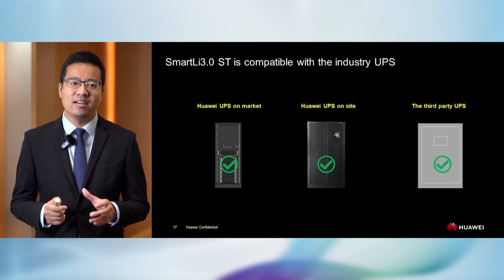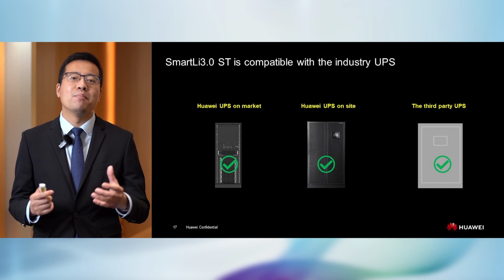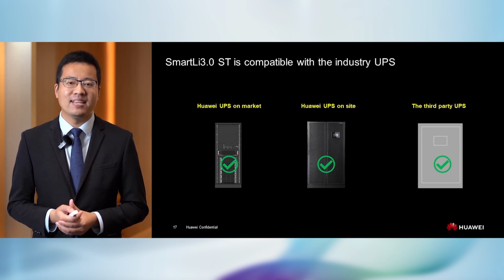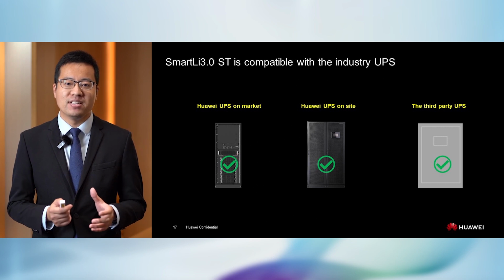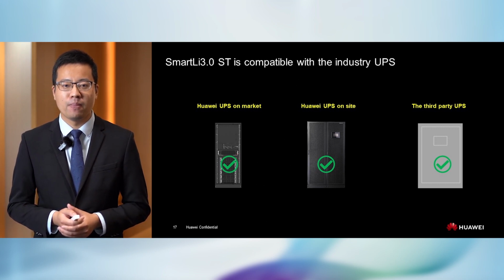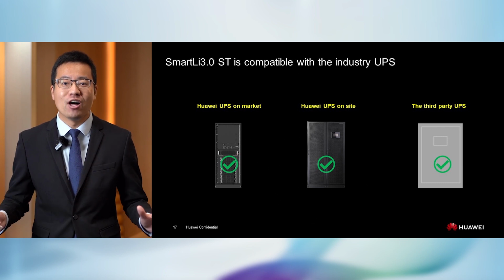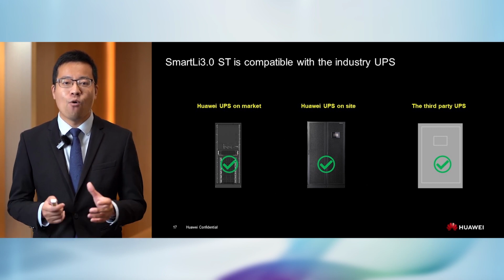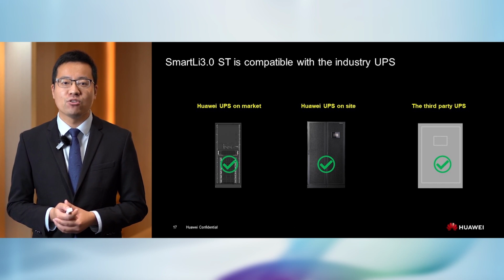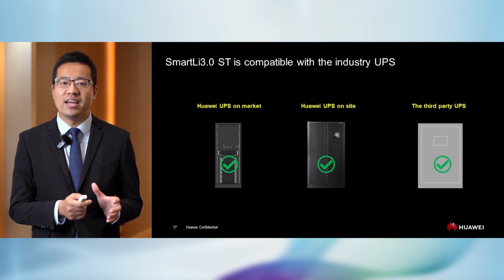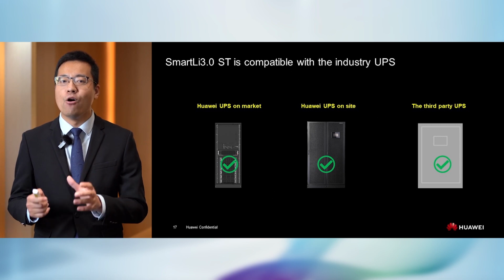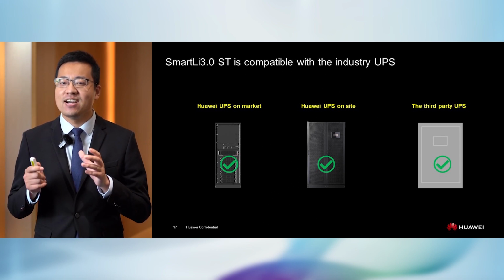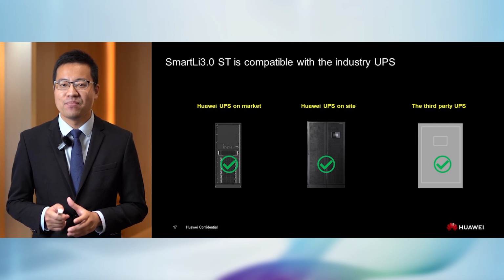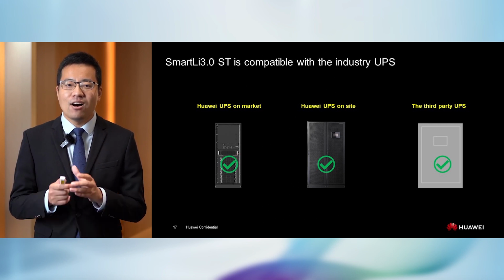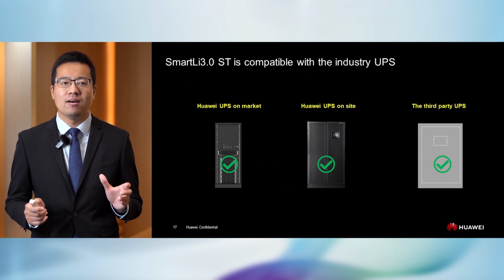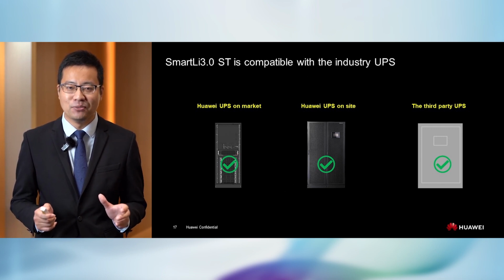In the industry now, it's not only new sites — more older sites need to replace lead-acid batteries with lithium-ion batteries. There's no need to replace all the batteries and UPSs, because Huawei SmartLi 3.0 can support not only Huawei UPS on the market, but also older Huawei UPS on site and third-party UPS on site. All of them are supported by SmartLi 3.0.